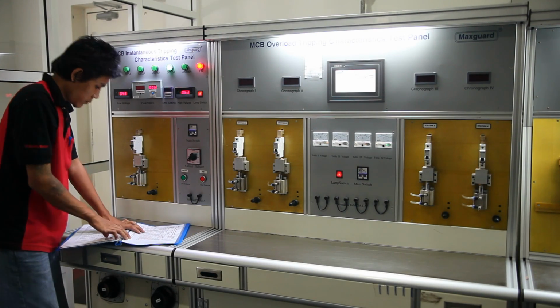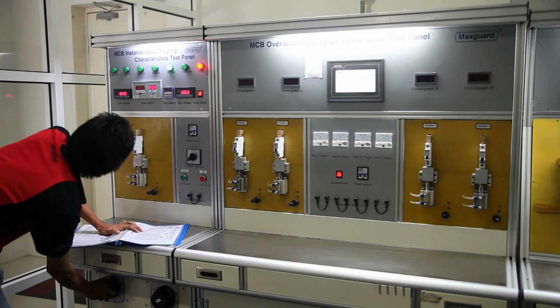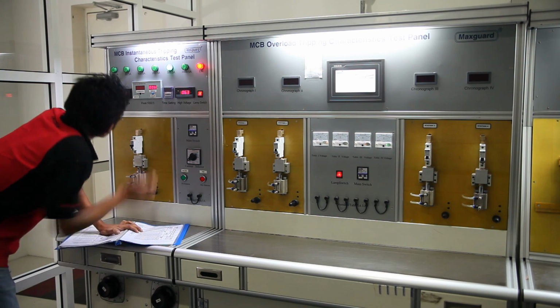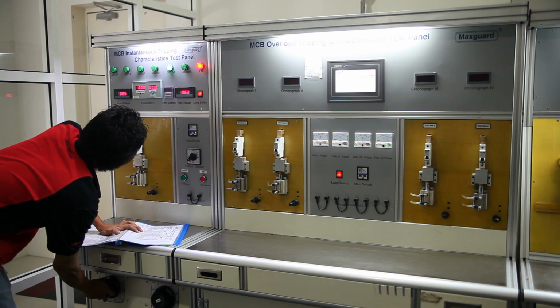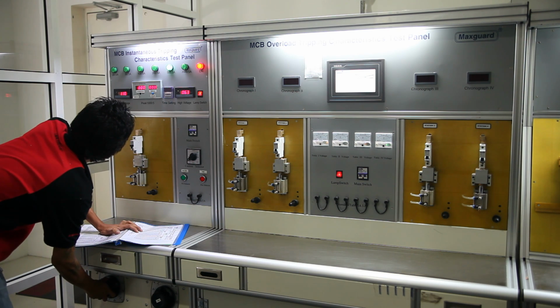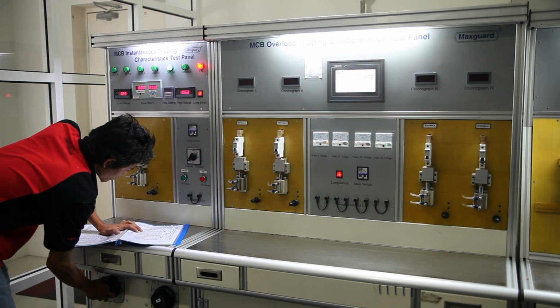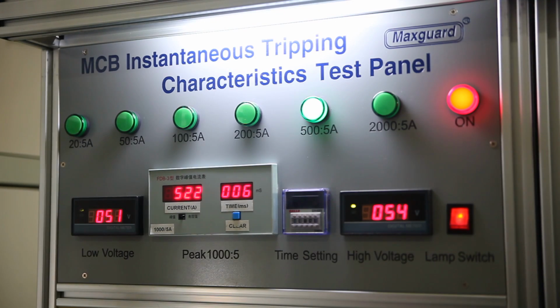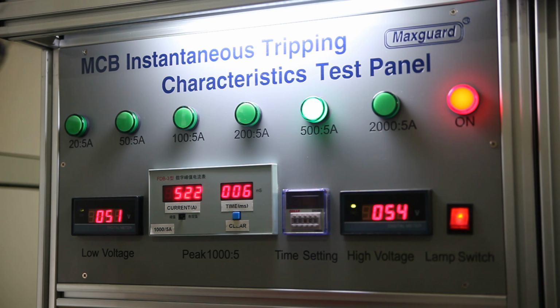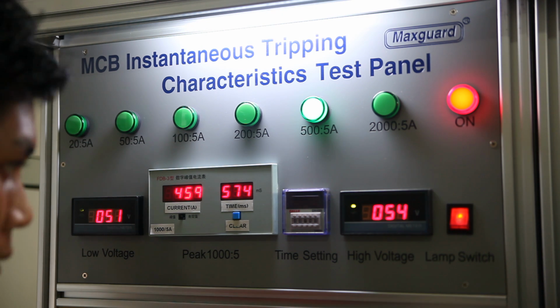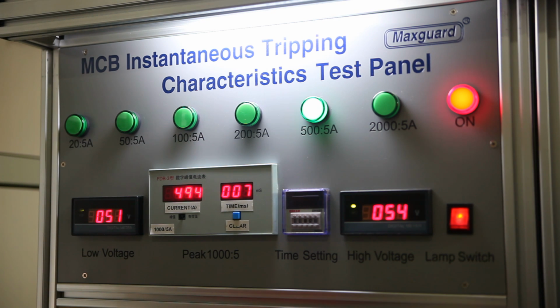Instantaneous tripping test for MCBs. Instantaneous tripping test is to verify electromagnetic tripping capability during short-circuit conditions. The time is designated to be 100 milliseconds. This test is to verify if MCBs can handle surge current and operate effectively to avert danger, and to determine that the instantaneous non-tripping and tripping time are above or below 100 milliseconds respectively.